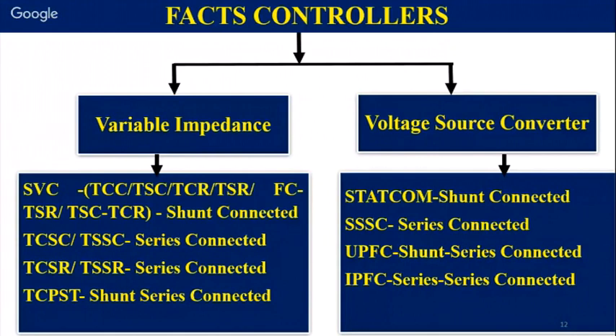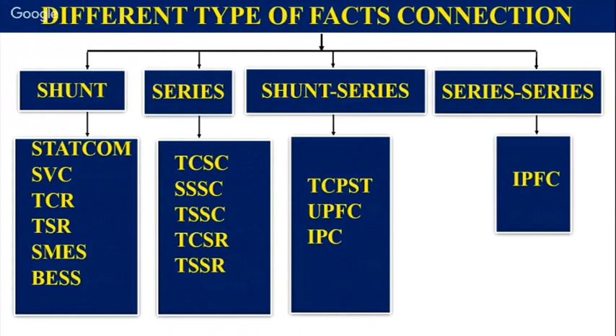So instead of using bulky components, which are very difficult to install, the effect is produced by converters and inverter action, which gives the same effect as the conventional compensating equipment. STATCOM is connected in shunt, and there are also series-connected and shunt-series-connected devices. UPFC has the advantages of both shunt and series connected FACTS. And IPFC is a series-connected voltage source converter. So again, here I have shown the classification according to the type of connection.